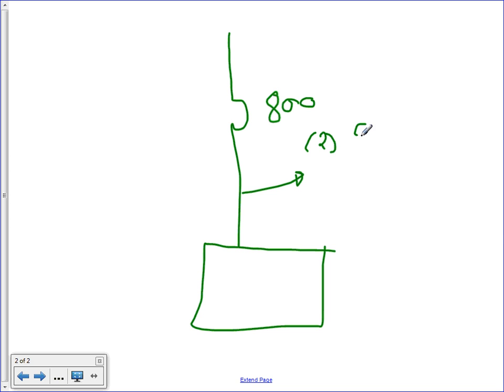Here's 2 sets of 500 kcmil, 2 sets, not 2 conductors, 2 sets. So if you take the 2, multiply by 380 for each 500 kcmil, from 310.15 B16, that will get you 760 amps.